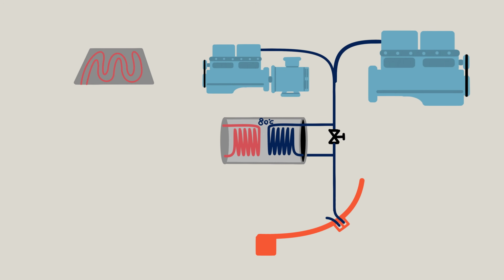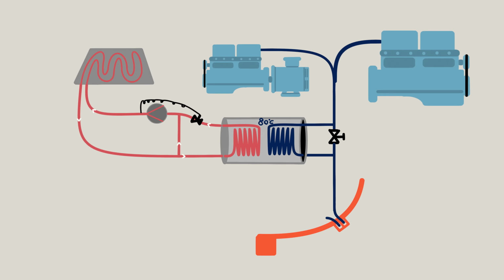The heated floors are on a separate loop. We cannot heat them with potable water straight from the tank, of course. And they only need water of 35 degrees Celsius. To extract that out of the buffer tank, the floor heating pump has two suction lines. One hot suction from the coil in the buffer tank and a cold one out of the return from the floors, which bypasses the buffer tank completely. By mixing them using a thermostatic valve, we get the desired 35 degrees Celsius.